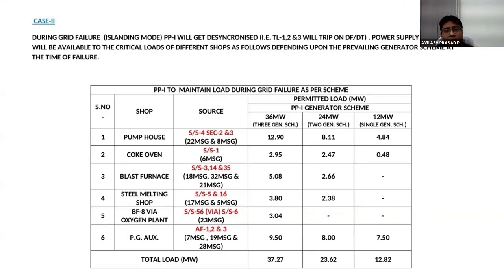If you see the last 3 rows, where permitted load per megawatt is given by PP1 generation scheme: if 3 generators are running, then we have 36 megawatt of load in which we run our pump house 22 MSG and 8 MSG for 12.90 megawatt. We will give 2.9 megawatt to our Coke Oven, that is substation 1, 6 MSG. We will give 5.08 megawatt to our blast furnace, that is substation 3, 14 and 35, that is 18 MSG, 32 MSG and 21 MSG.